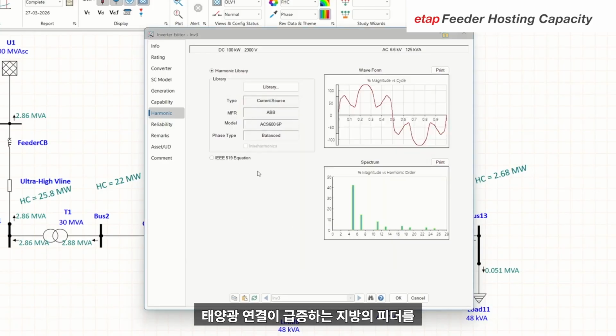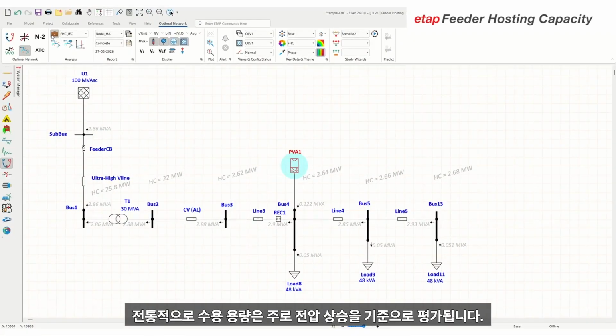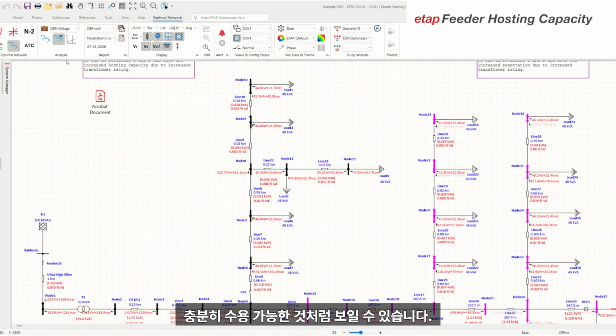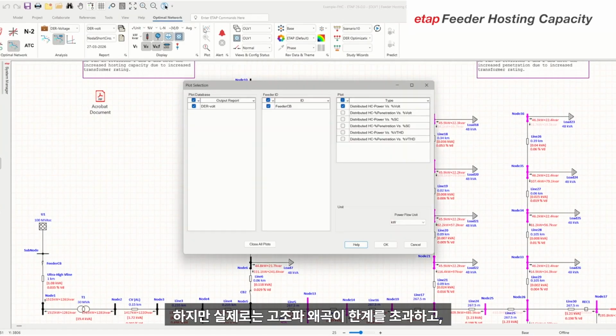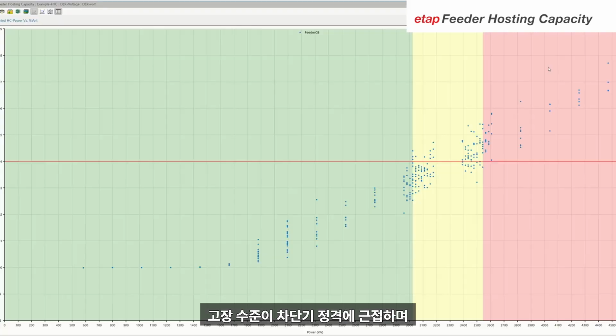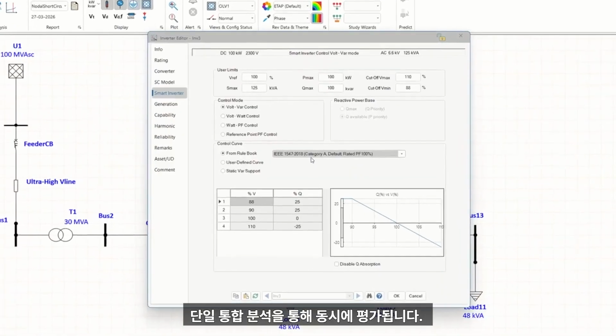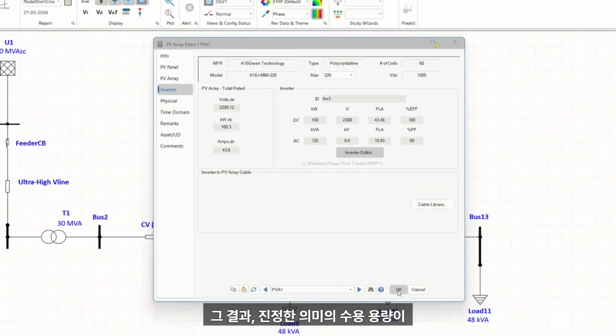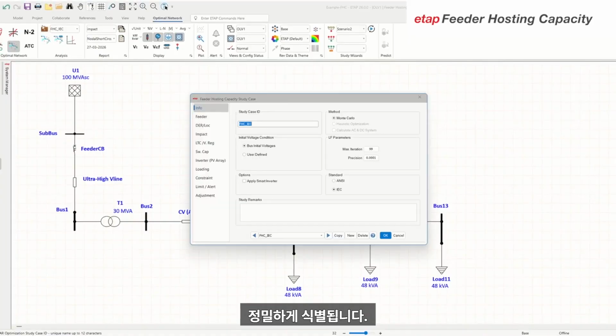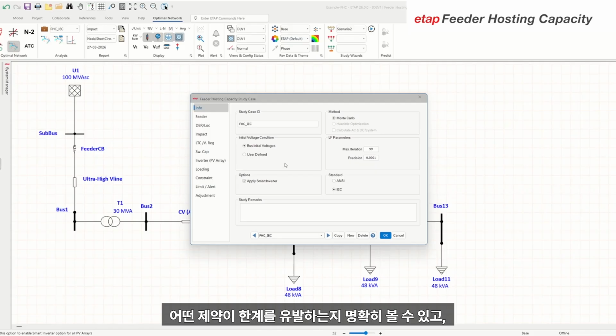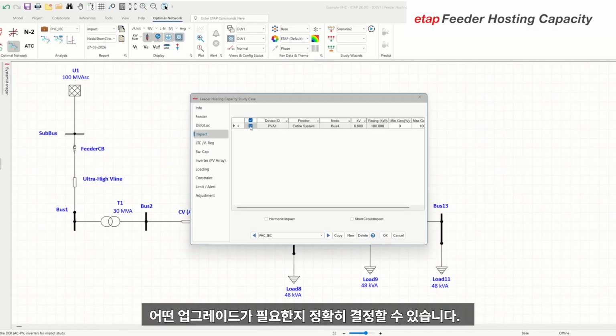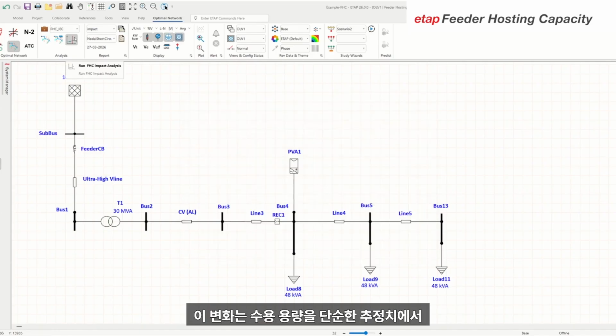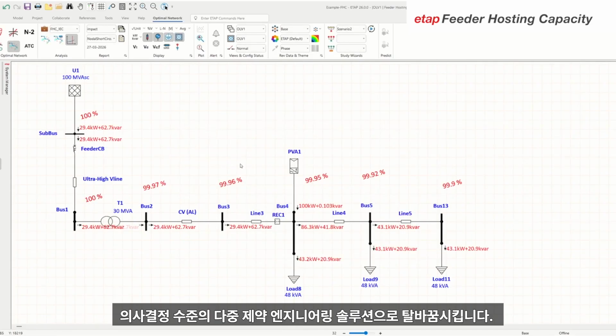Consider a utility evaluating a rural feeder with rapidly growing solar PV connections. Traditionally, hosting capacity is assessed primarily on voltage rise, and as a result, the feeder appears capable of accepting additional megawatts. But in reality, harmonic distortion exceeds limits. Fault levels approach breaker interruption ratings, and protection coordination margins are reduced. With ETAP 2026, all of these constraints are evaluated simultaneously in a single unified analysis. The result? The true hosting capacity is identified with precision. The exact limiting constraint is clearly visible, and engineers can determine what upgrades unlock additional capacity. This transforms hosting capacity from a simplified estimate into a multi-constraint decision-grade engineering solution.